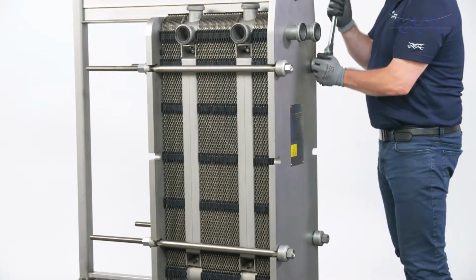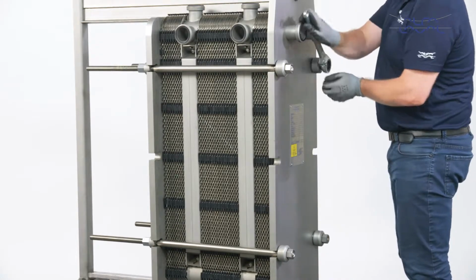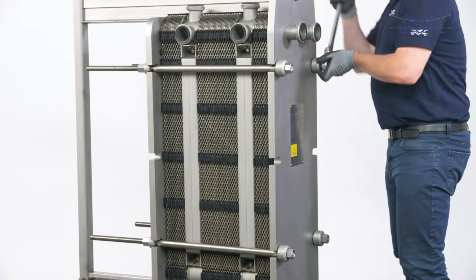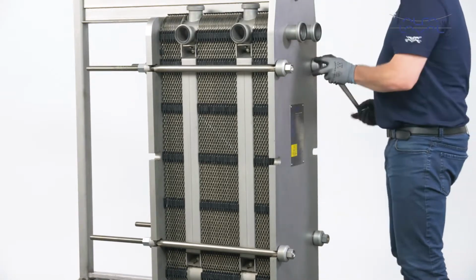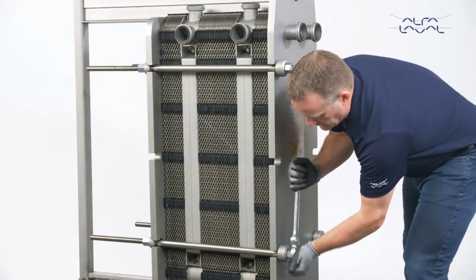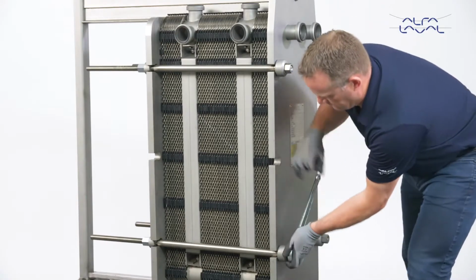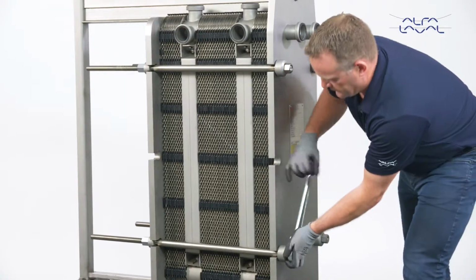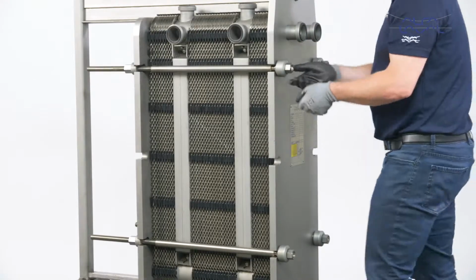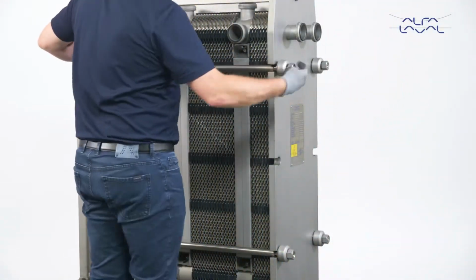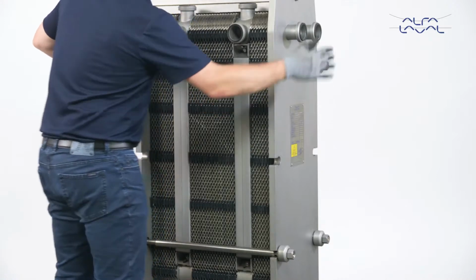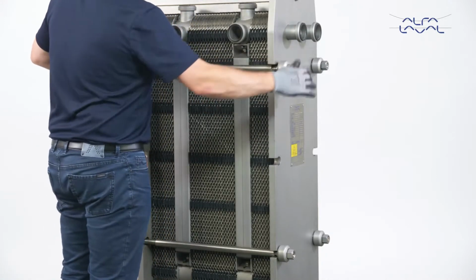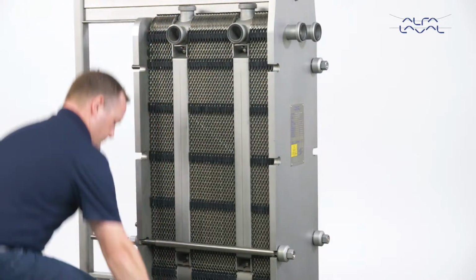Skewing of the pressure plate during opening must not exceed 10 mm across the width, which is equivalent to 2 turns per bolt, and 25 mm along the height of the unit, which is equivalent to 5 turns per bolt. Continue loosening the bolts until all reaction forces on the plate pack have disappeared. Then remove the bolts.